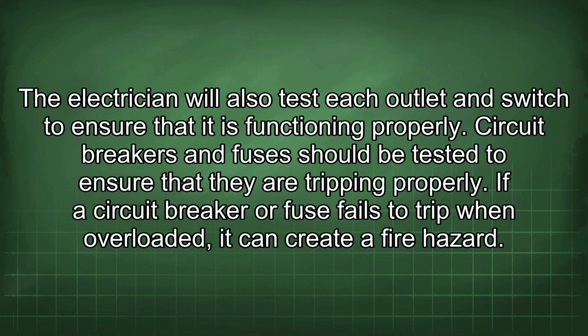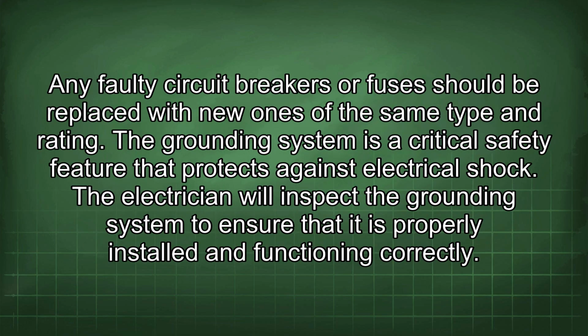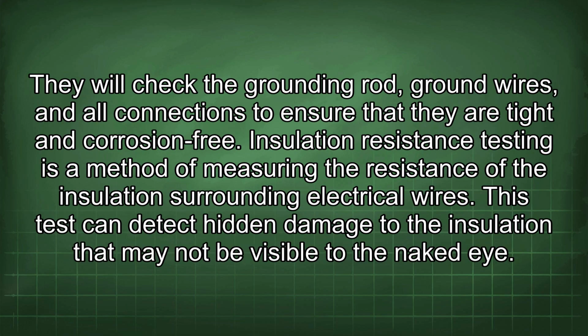Circuit breakers and fuses should be tested to ensure that they are tripping properly. If a circuit breaker or fuse fails to trip when overloaded, it can create a fire hazard. Any faulty circuit breakers or fuses should be replaced with new ones of the same type and rating. The grounding system is a critical safety feature that protects against electrical shock. The electrician will inspect the grounding system to ensure that it is properly installed and functioning correctly. They will check the grounding rod, ground wires, and all connections to ensure that they are tight and corrosion-free.